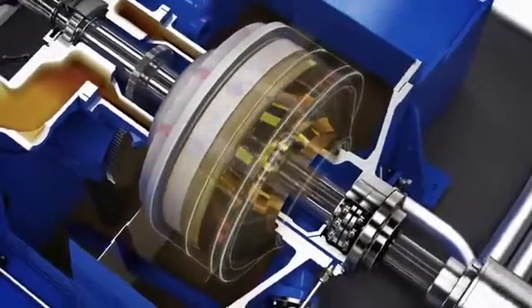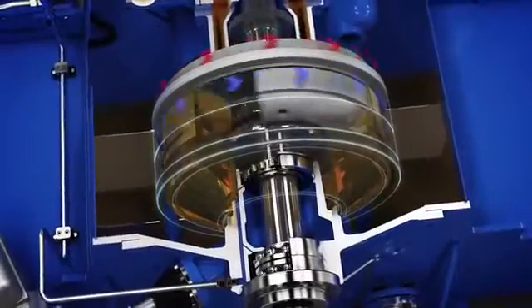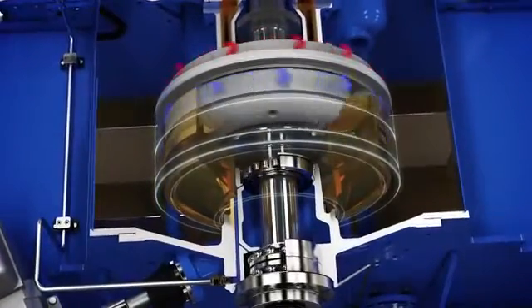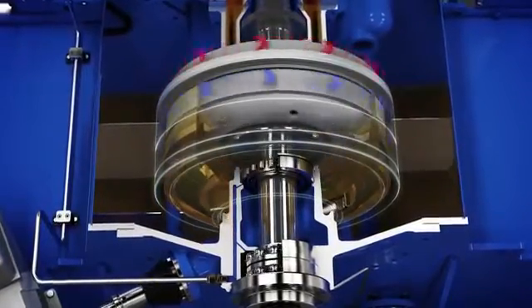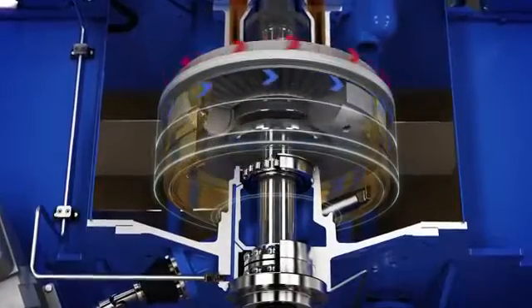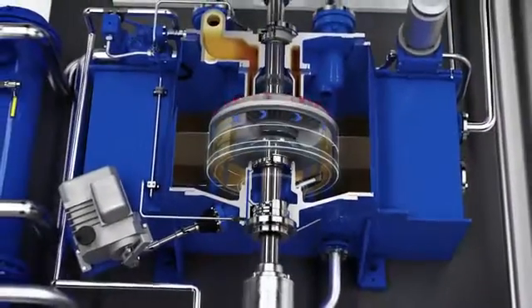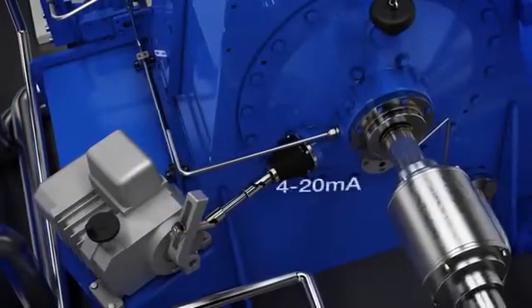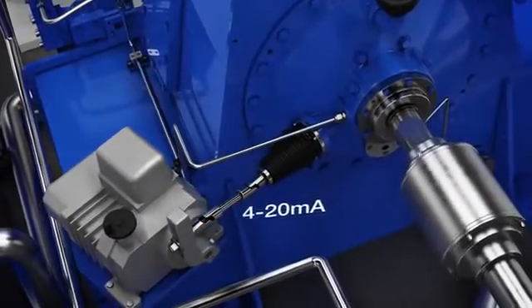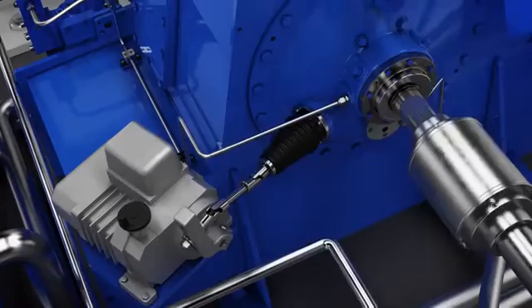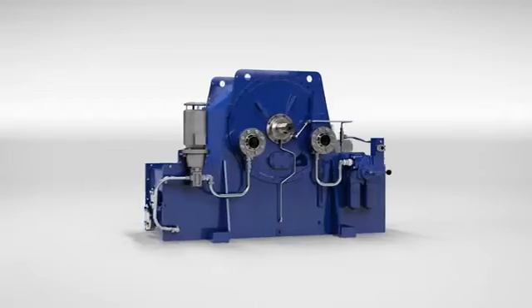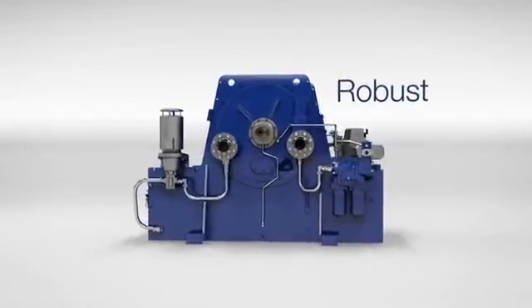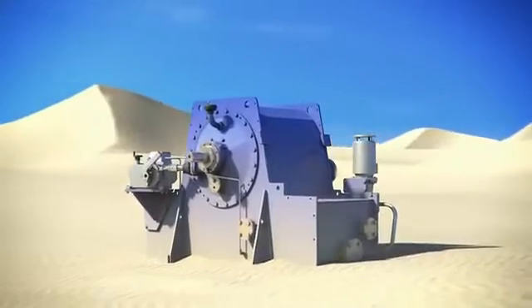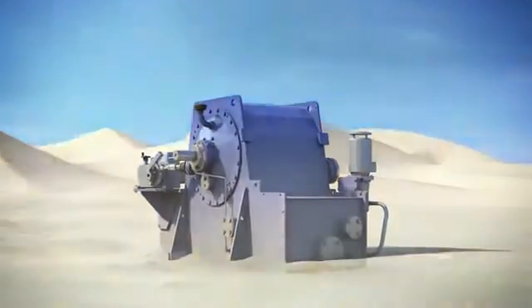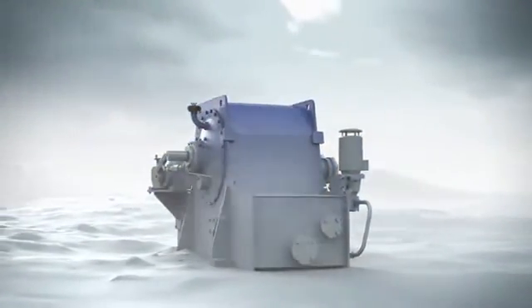The pump speed is controlled by the oil fill level in the coupling. This is done using a scoop tube that extends or retracts in order to change the fill level. A 4 to 20 milliampere signal is all that is needed to control it. This makes integrating it into the power plant control system a simple matter. Its robust construction makes the Voith variable speed coupling ideal for outdoor use and deployment under extreme climate conditions.